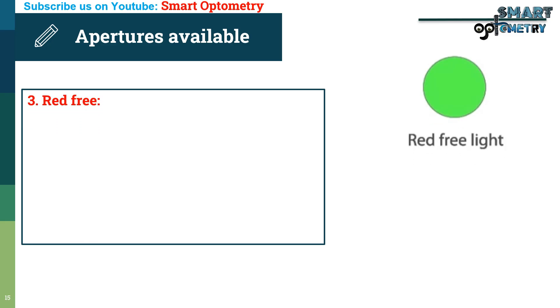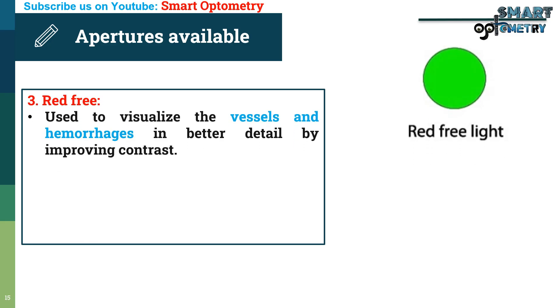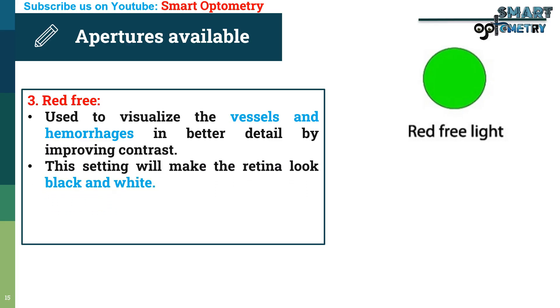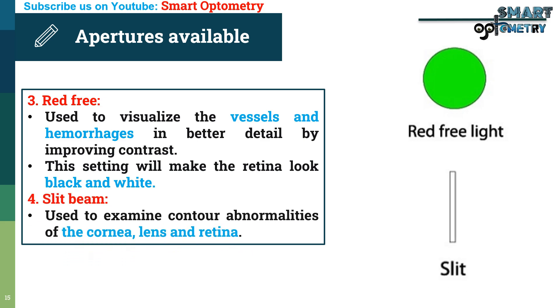3. Red-free circle: it is used to visualize vessels and hemorrhages in better detail by improving contrast. This setting will make the retina look black and white. 4. Slit beam: it is used to examine contour abnormalities of the cornea, lens, and retina.